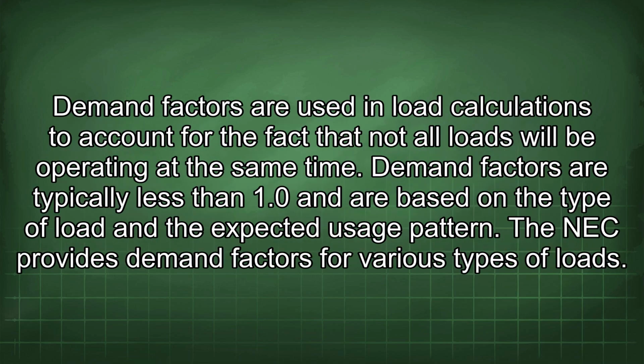Demand factors are used in load calculations to account for the fact that not all loads will be operating at the same time. Demand factors are typically less than 1.0 and are based on the type of load and the expected usage pattern. The NEC provides demand factors for various types of loads.